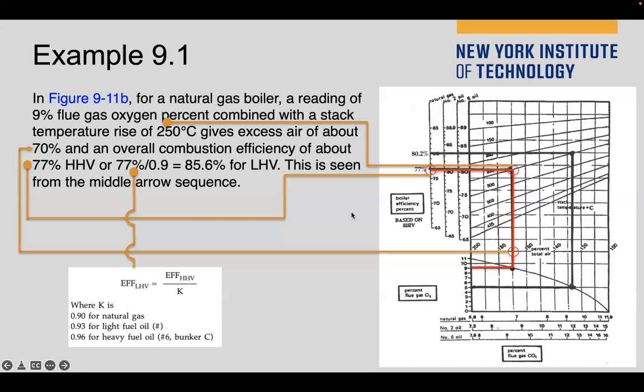So let me illustrate it one by one. First, this sentence gives me the reading of the flue gas, 9% oxygen. So every time we start from here, the flue gas percentage of oxygen, we start at 9%, and we draw a horizontal line that touches this curve - that's the first point. Then we draw a vertical line, and it will intersect the line of the percentage of the total air, giving me the first indicator of the percentage of the air.